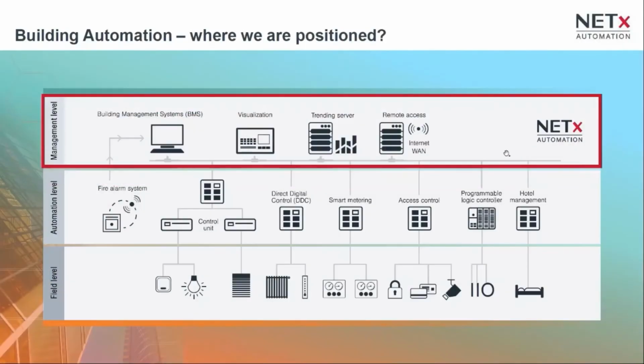I would like to continue with the positioning and give you a more detailed overview about our products as well. You know, on the field automation, you have KNX actuators, you will have KNX DALI lighting systems, you will have maybe HVAC systems based on BACnet, you will have Modbus for air conditioning, metering as well.